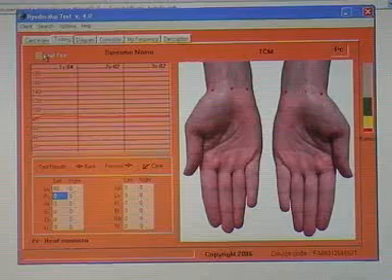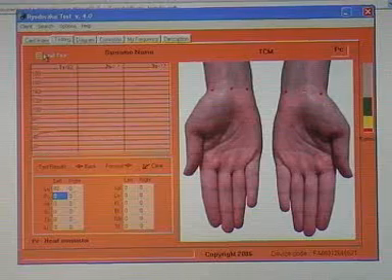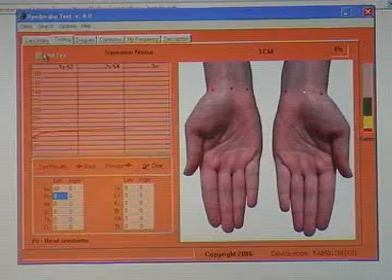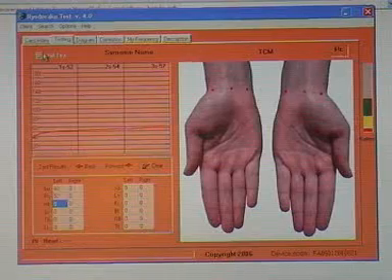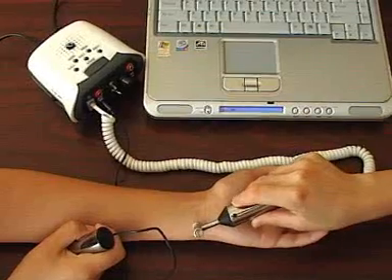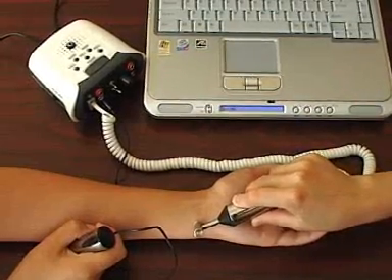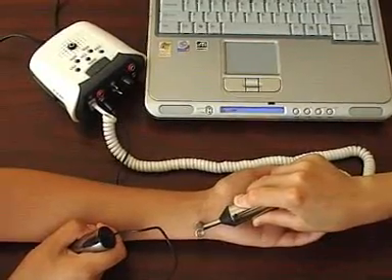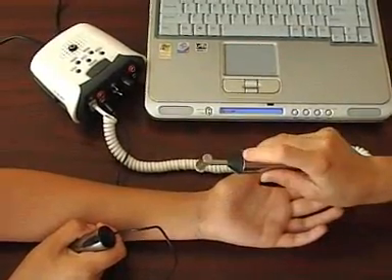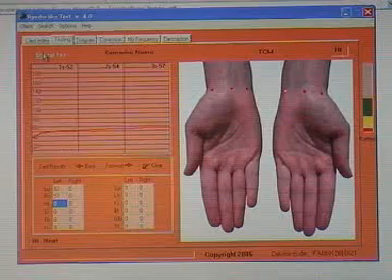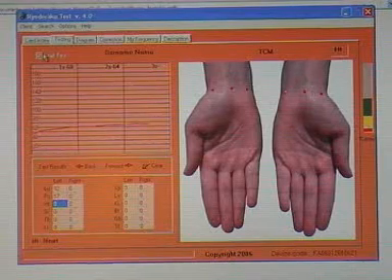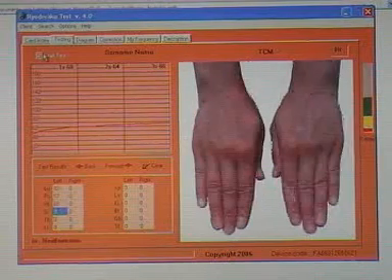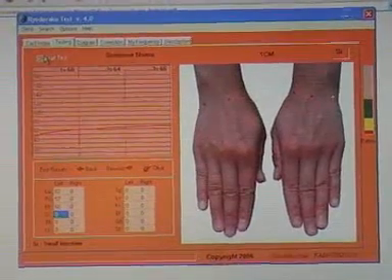Since that moment the reading begins. The red line steadily rises to a certain value where it gradually stabilizes. The measurement of each point is performed within 3 seconds. After 3 seconds you need to press the small black push button on the detecting probe.